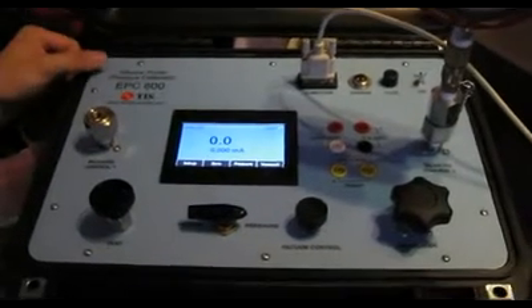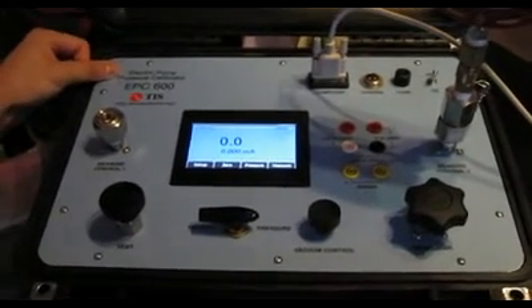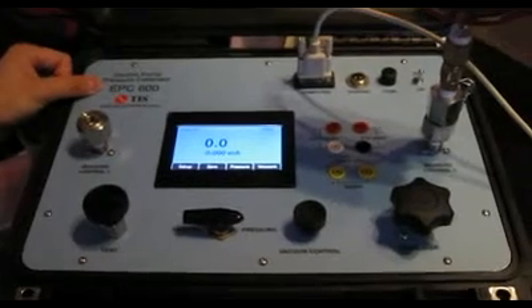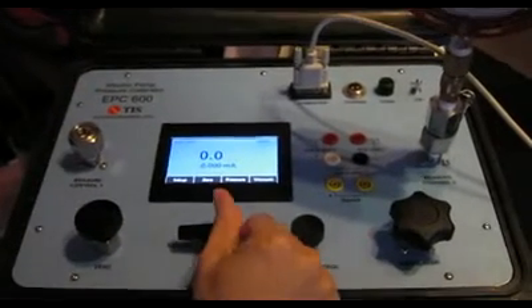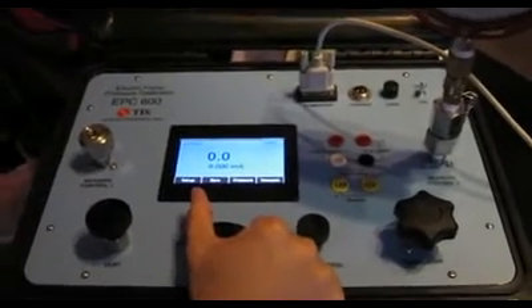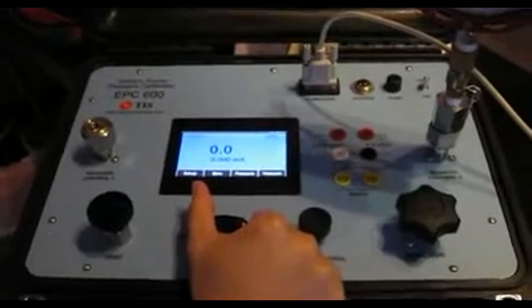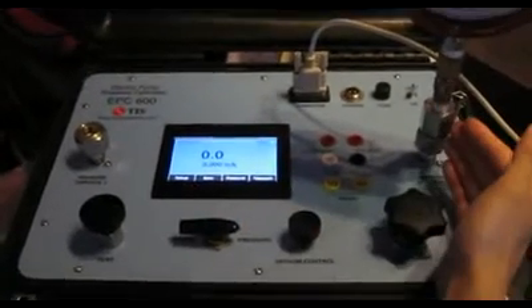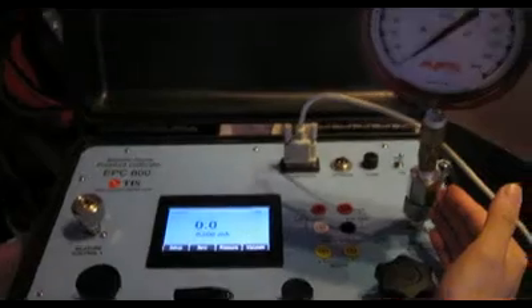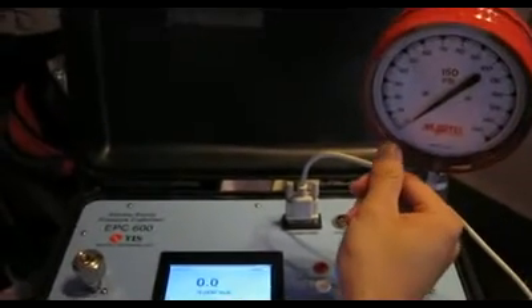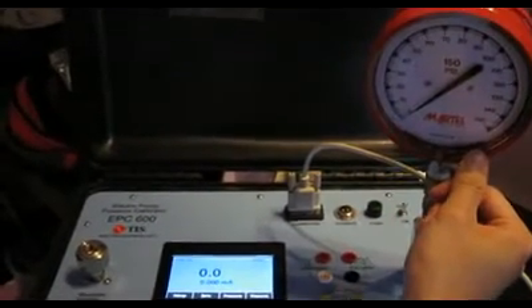This is a demo for our electric pump pressure calibrator EPC600. It is able to generate vacuum minus 0.9 to 70 bar. We are using it to calibrate an analog pressure test gauge with a range from 0 to 150 psi.